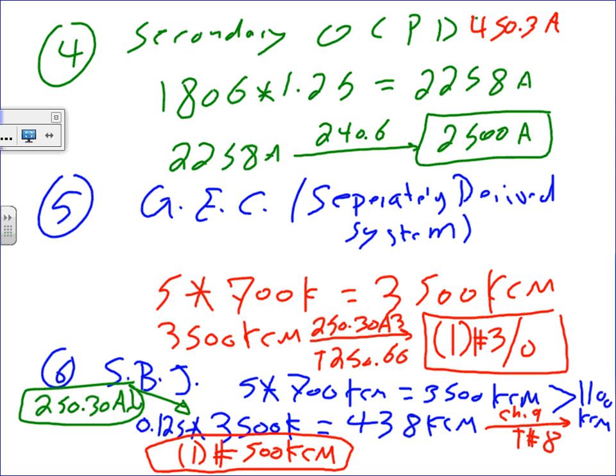Any question, guys, about the grounding electrode conductor for the separately derived system? System bonding jumper. Why didn't I write system bonding jumper for the separately derived system? Because the system bonding jumper is always for the separately derived system. The grounding electrode conductor could be for the service or could be for the separately derived system. So this is the SBJ: the system bonding jumper is always for the separately derived system.